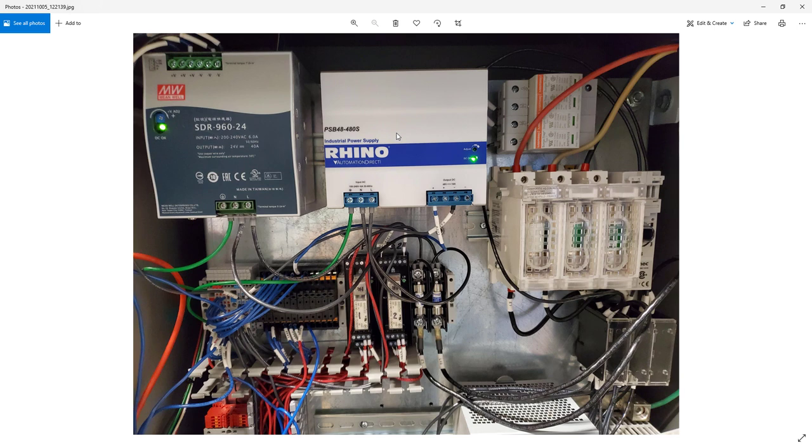So you see we have a 24 volt Meanwell and a Rhino 48 volt. What happened was the stepper motors, and keep in mind that there were not necessarily any legitimate calculations done for load torque for the devices that are being rotated by the stepper motors. So when I commissioned the NEMA 34 motor which was 1100, the biggest one they make that company, I got erratic behavior from the device that was rotating. What I discovered was that the load in inch pounds or inch ounces to rotate that was greater than what the stepper motor would provide.